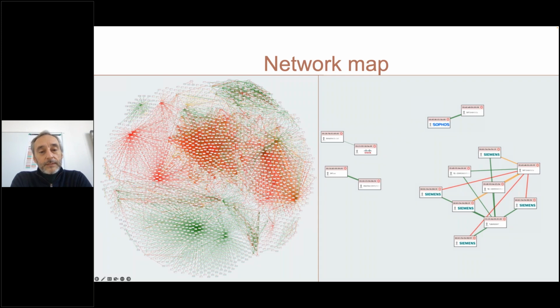Looking deeper into this, we found many TCP retransmissions, many TCP quality issues, and this can be tracked down to a faulty Ethernet cable - a failure in the grounding of the Ethernet cable. It's not a total failure, but it creates communication incidents every now and then, which create the TCP retransmissions we detect. So even though the process was working well, it was fragile and perhaps on its way to fail at a certain time.